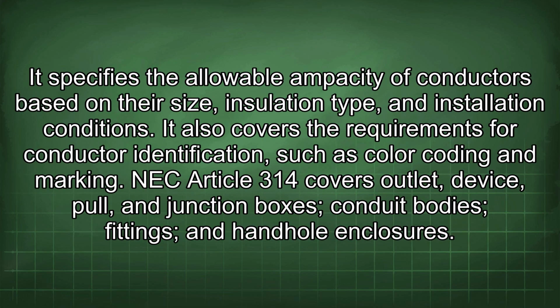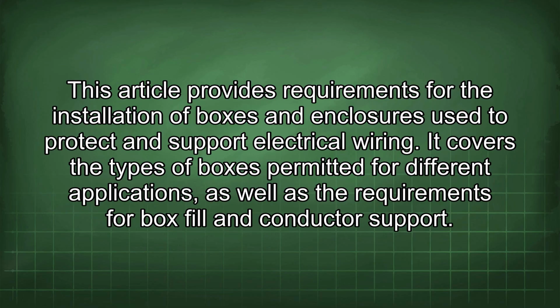It specifies the allowable ampacity of conductors based on their size, insulation type, and installation conditions. It also covers the requirements for conductor identification, such as color coding and marking. NEC Article 314 covers outlet, device, pull, and junction boxes, conduit bodies, fittings, and handhole enclosures. This article provides requirements for the installation of boxes and enclosures used to protect and support electrical wiring.